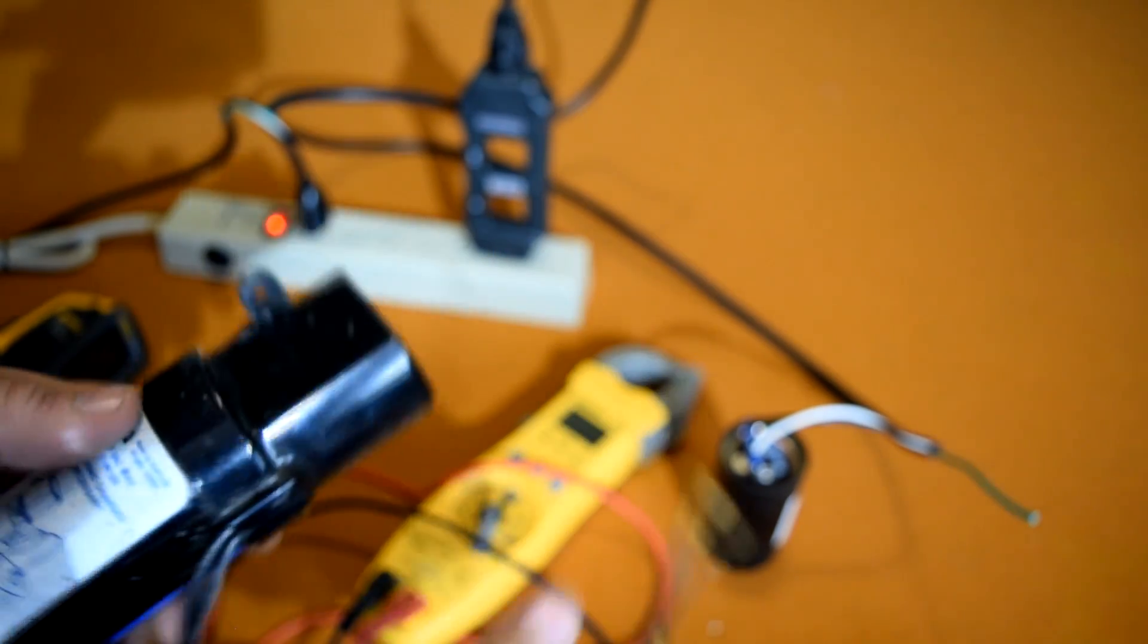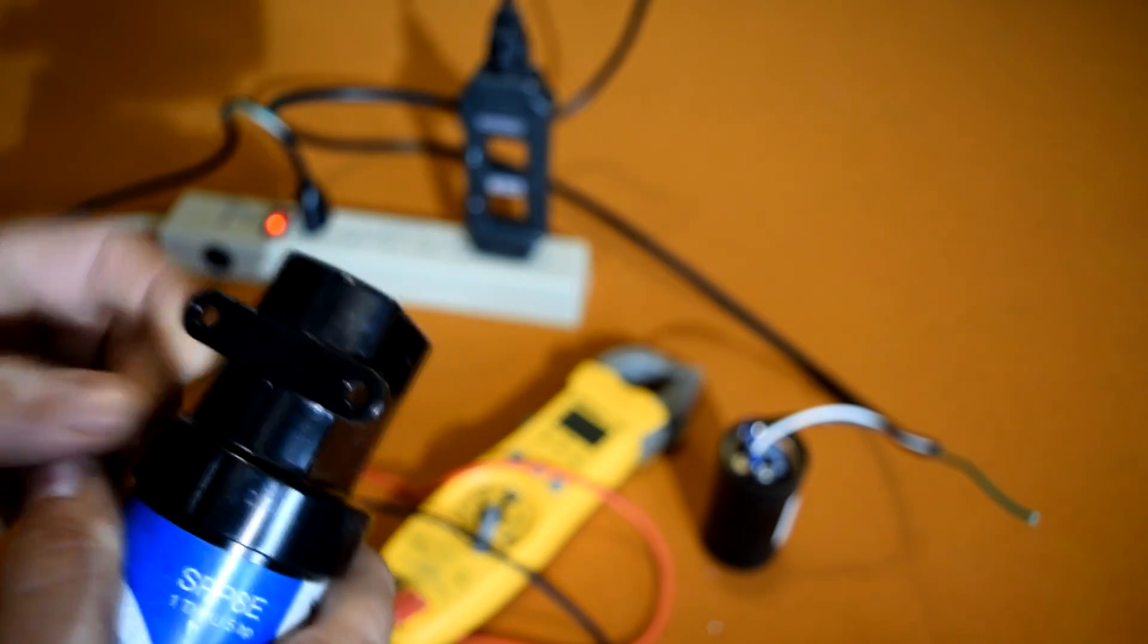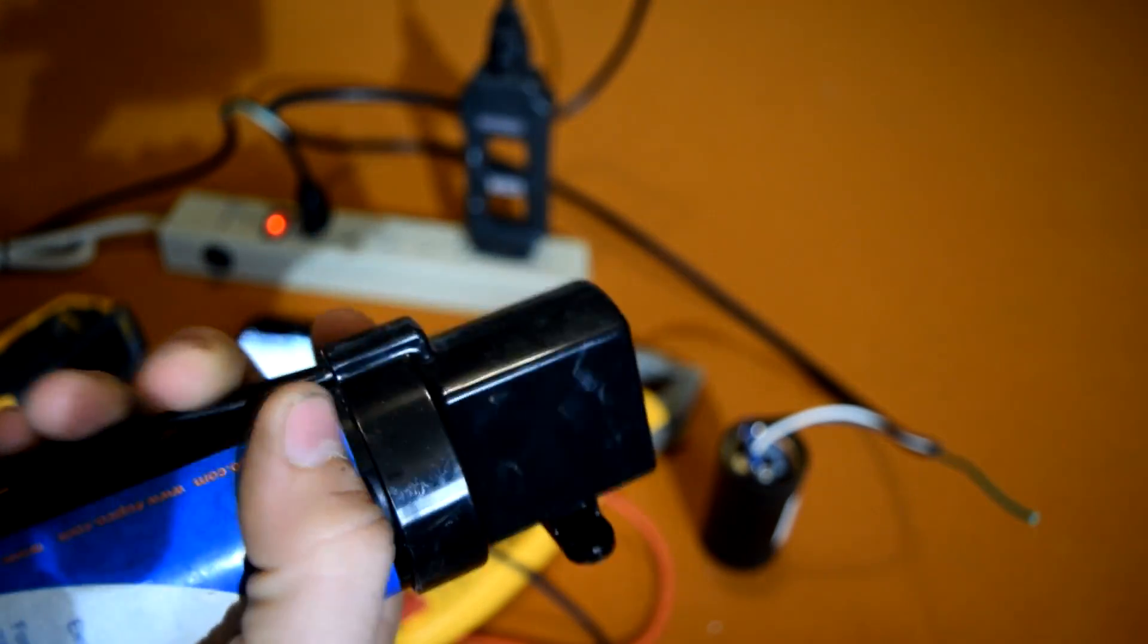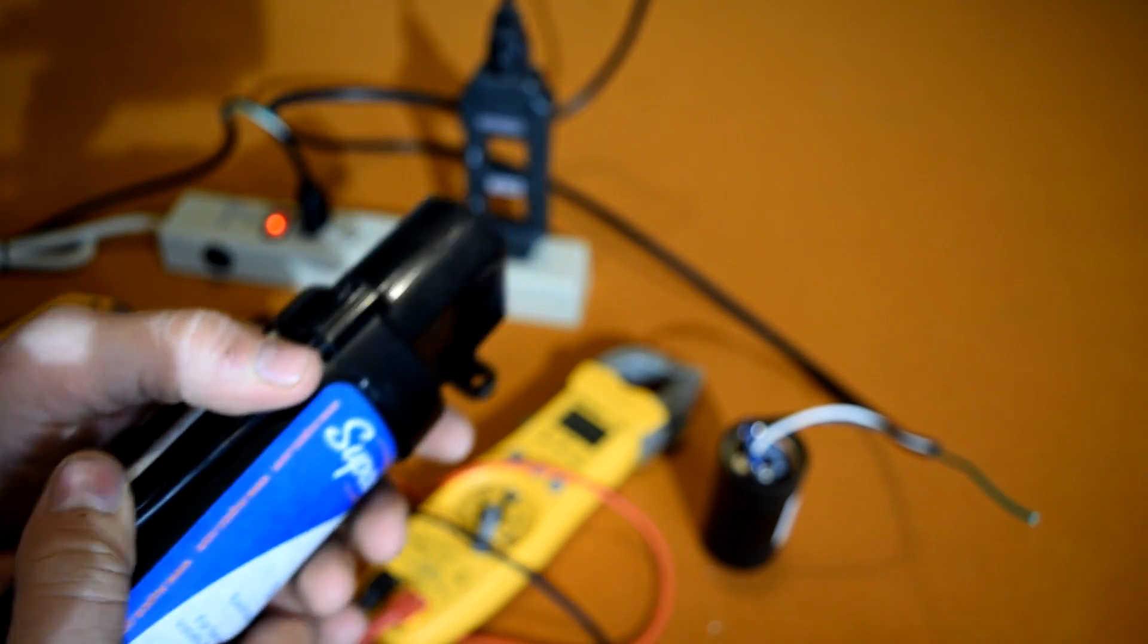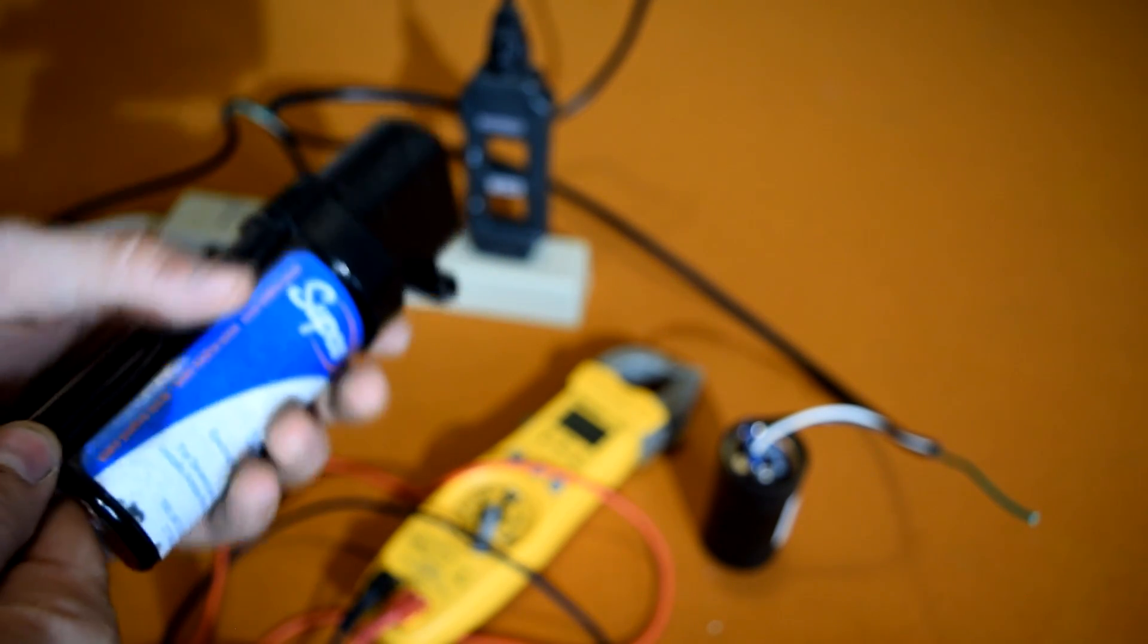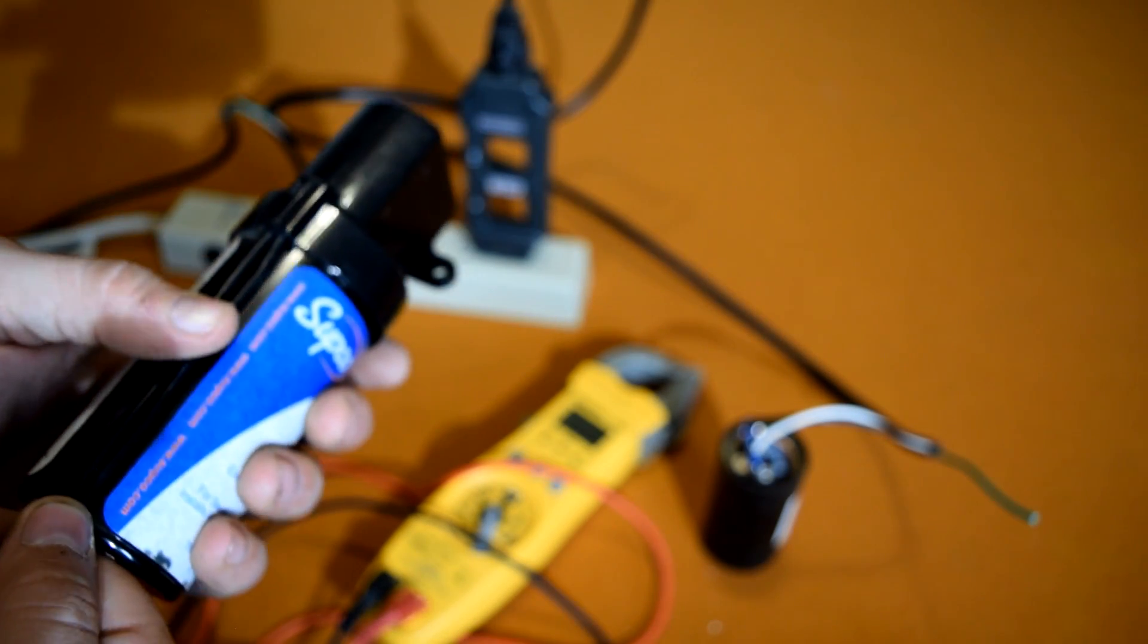The benefit of this is it will start your compressor quickly. The drawback is it will kill your compressor quickly. Over a period of time, you're going to lose your compressor's resistance inside of the start windings, which is going to kill it. Nobody wants their compressor to go bad because they're expensive to replace.